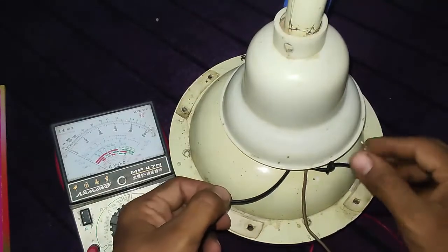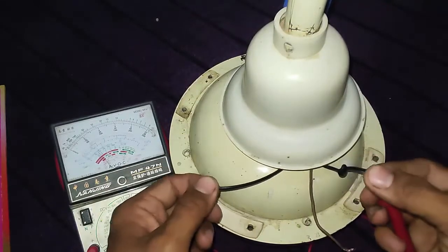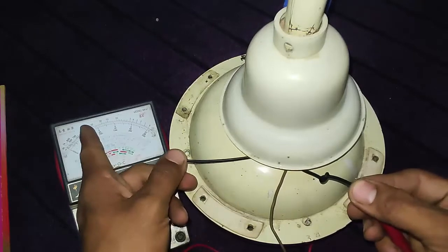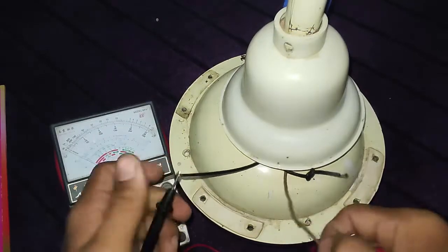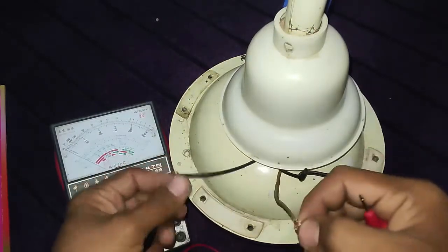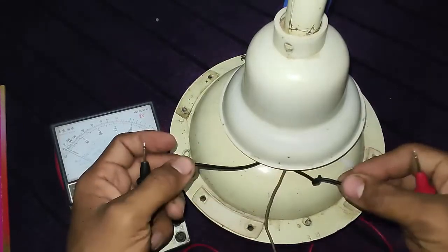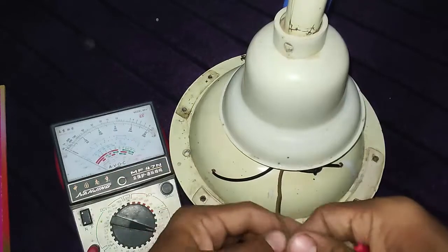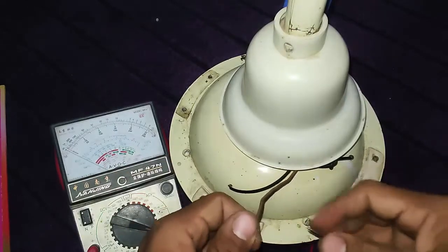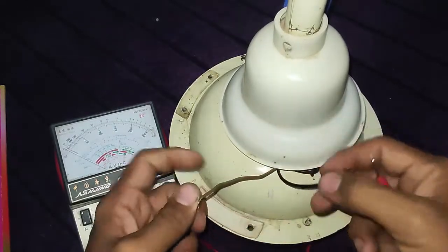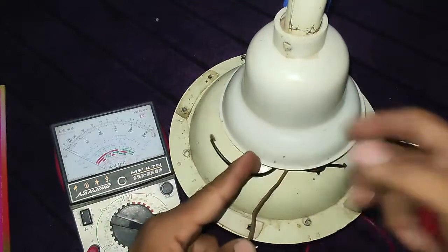These two wires have high resistance, so this one is common, because these two wires have high resistance with one another and the third will be common. The common and the running resistance will be low and the common and starting resistance will be high.